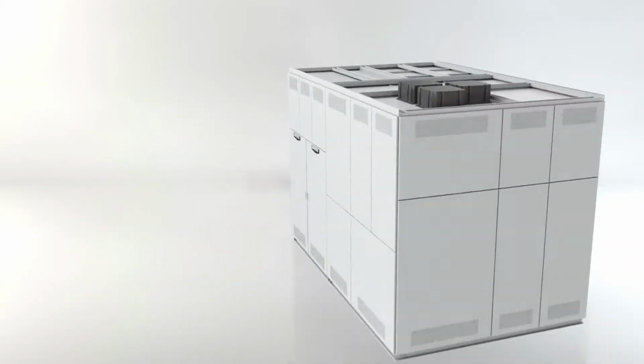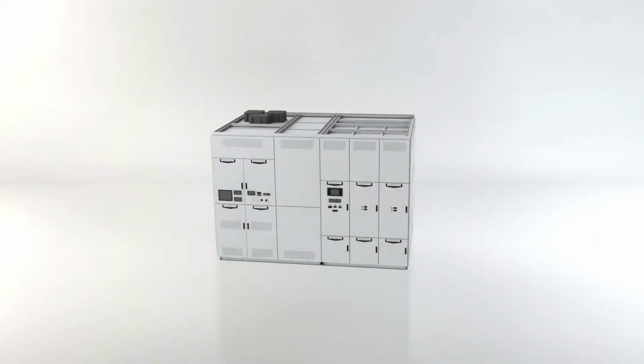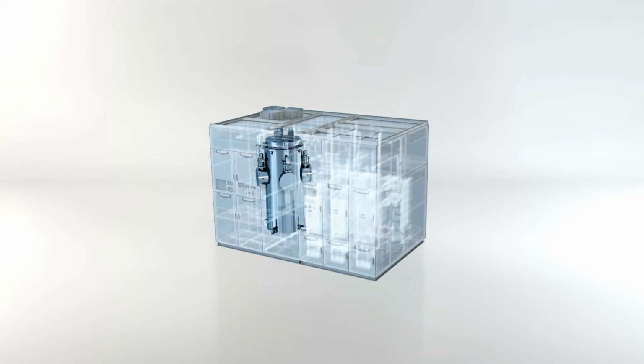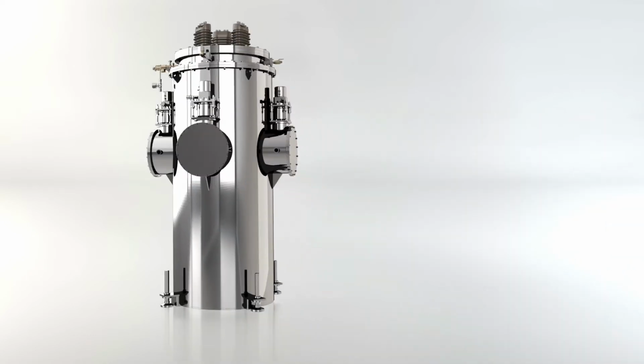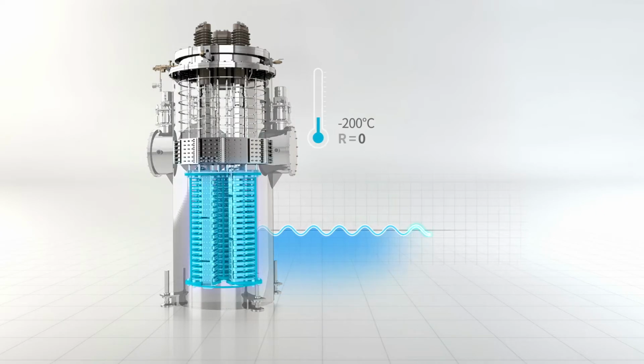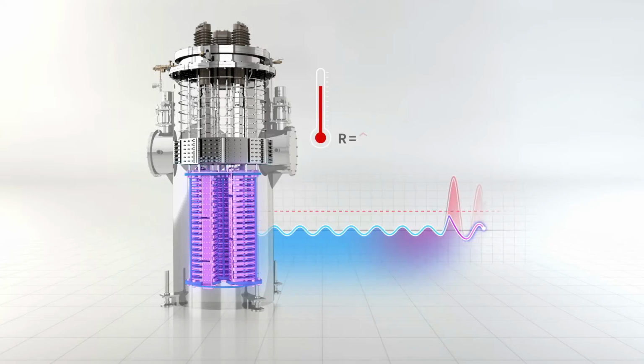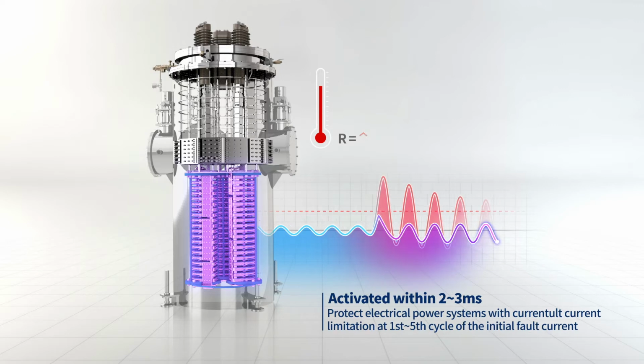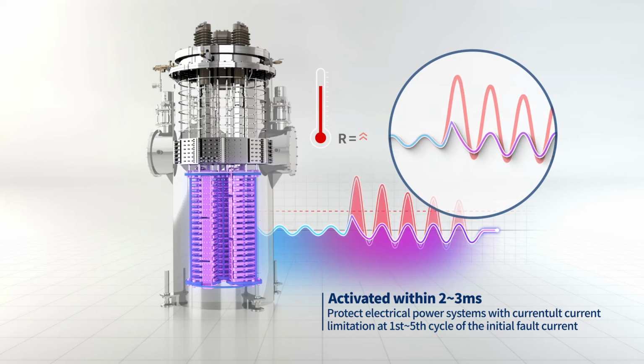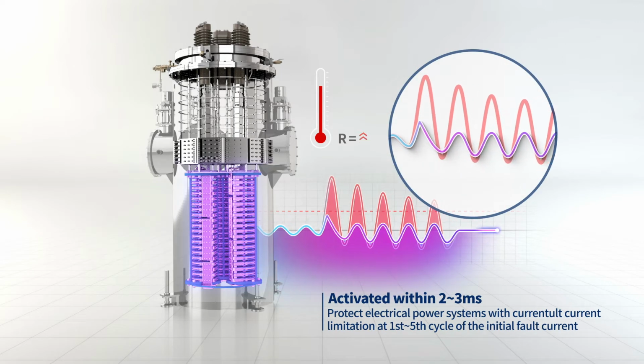Superconducting Fault Current Limiter is the solution to resolve these issues. SFCL, electrical power equipment that utilizes changes in physical properties of the superconductor. The principle is that in usual times, it does not impact the system. But when a fault current occurs, SFCL is activated without relaying a signal, so that the scale of the fault current is reduced before the circuit breaker is operated.